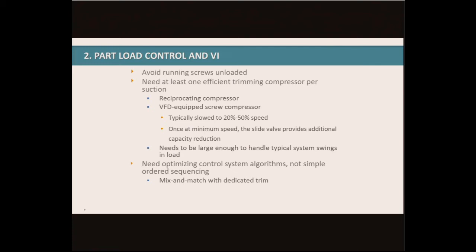We want to make sure that one compressor per suction group is dedicated as a trim compressor, and we want that compressor to be the most efficient one. Reciprocating compressors, although there aren't too many out there anymore, have really good part load performance — at 50% load, they use about 50–52% power, making them a very good trim compressor. If you have a screw compressor with a VFD, that's going to be your most efficient screw compressor and the one you want dedicated as your trim compressor for that suction.